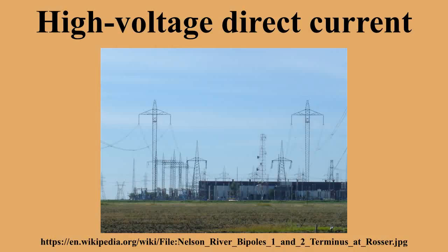On March 15, 1979, a 1,920 MW thyristor-based direct current connection between Cahora Bassa and Johannesburg was energized. The conversion equipment was built in 1974 by Allgemeine Elektricitäts-Gesellschaft AG, and Brown, Boveri & Cie and Siemens were partners in the project. The late completion date was the result of the civil war. The transmission voltage of plus or minus 533 kV was the highest in the world at the time.